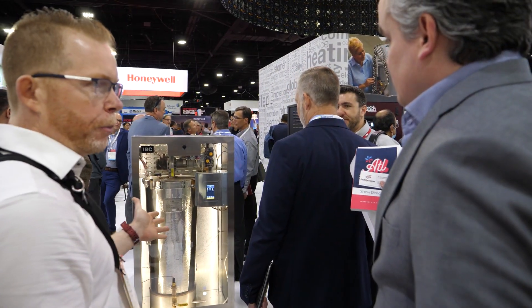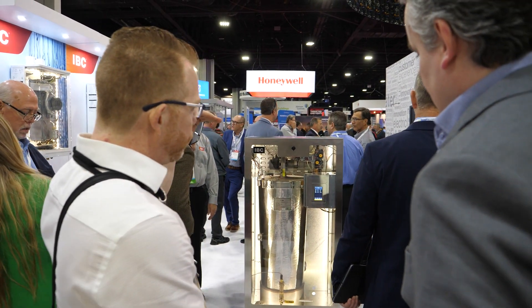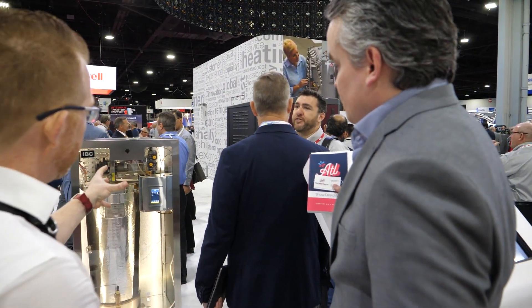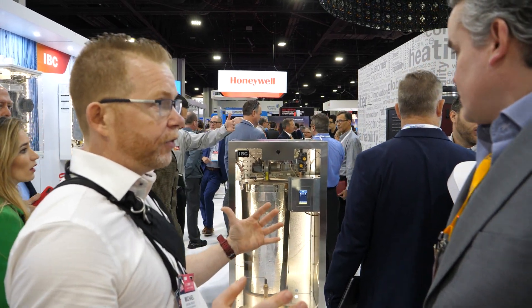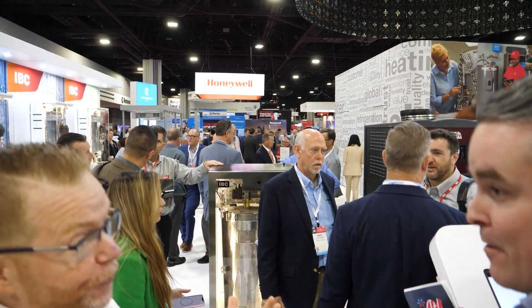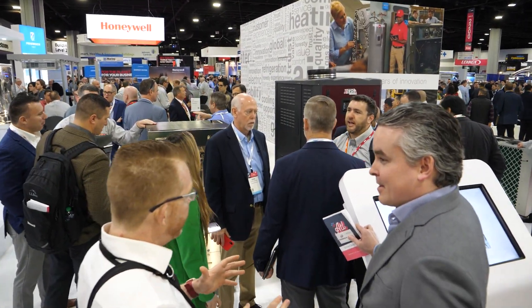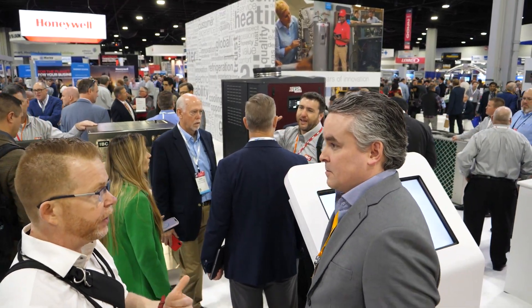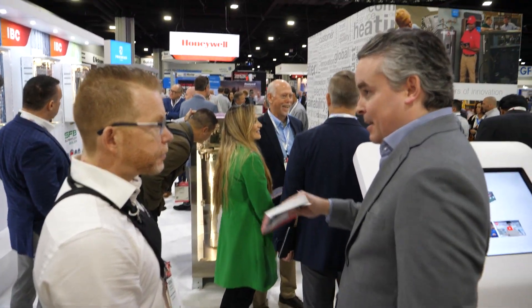They're all the same basic cabinet size — nice and roomy and easy to service, very user-friendly for the contractor. What stands out to me is that simplicity: find a commercial boiler where you can tell there are fewer than ten parts — it's so clean and concise. There's a large fire tube heat exchanger, gas pressure switches built in, and that integrated V10 control. You can cascade up to 24 units together, and we've done large commercial jobs with six, seven, or eight of these tied together — the built-in BACnet is amazing for that.